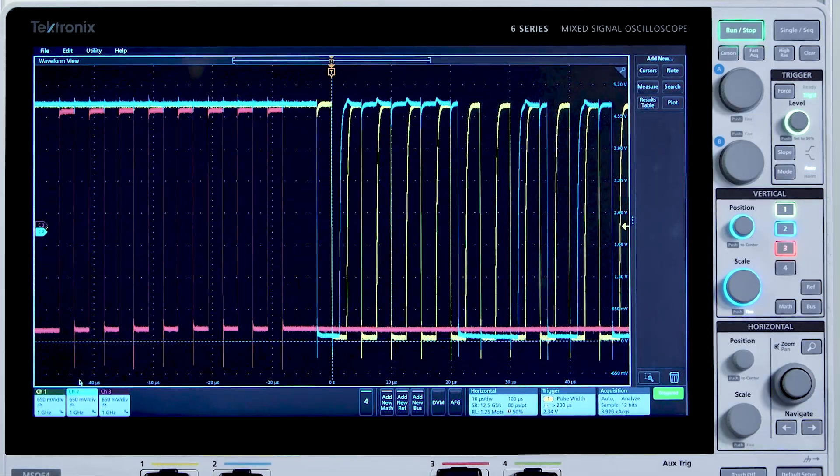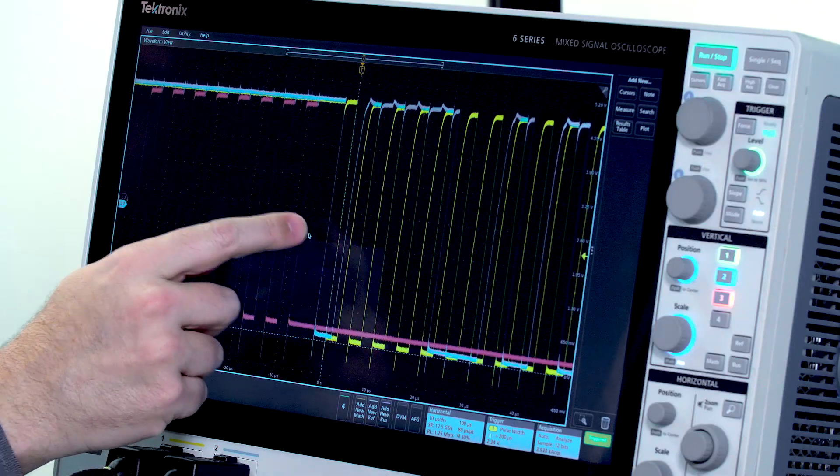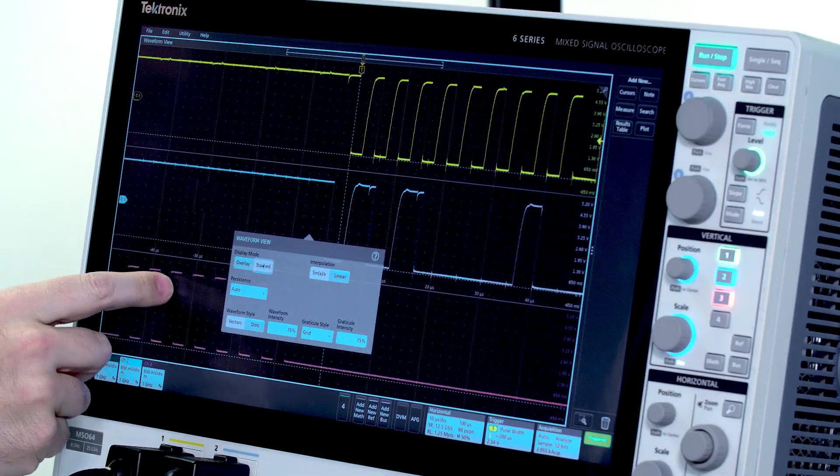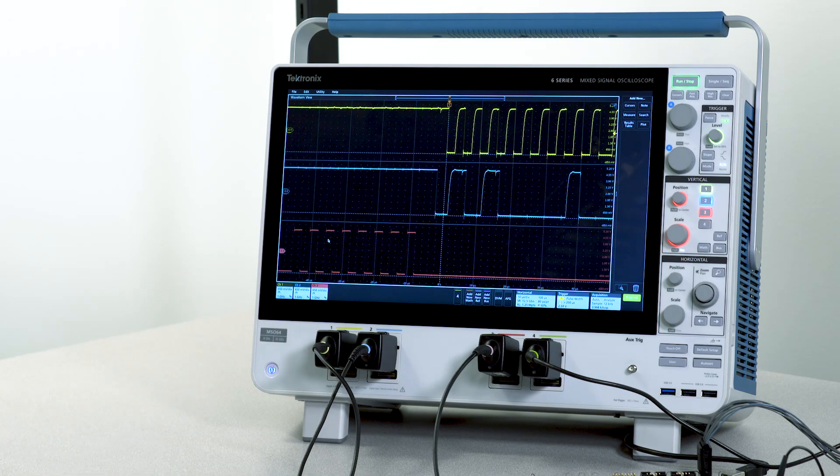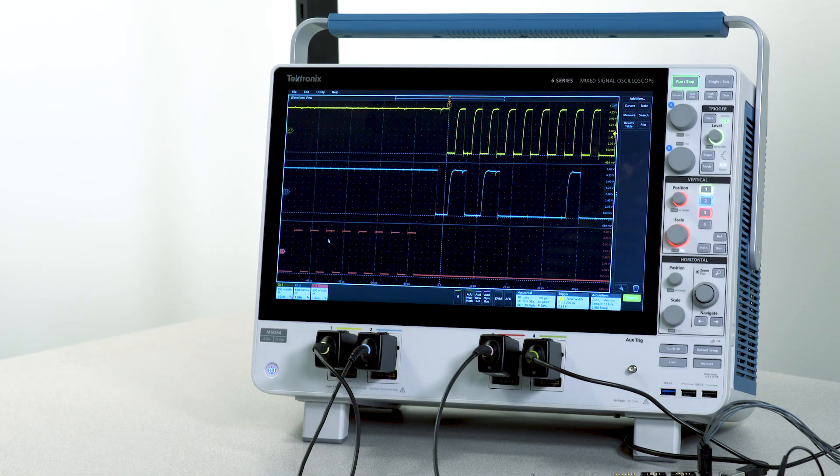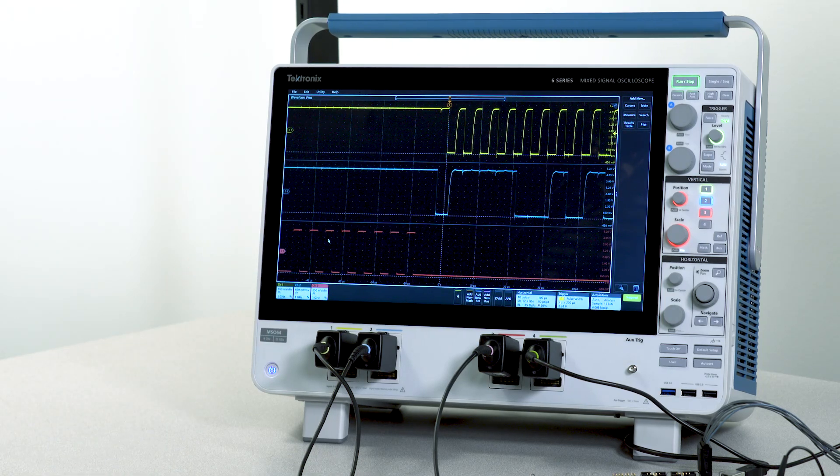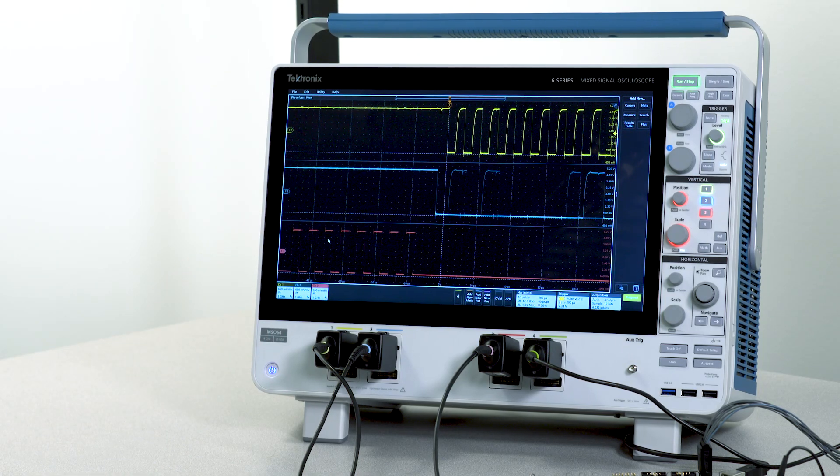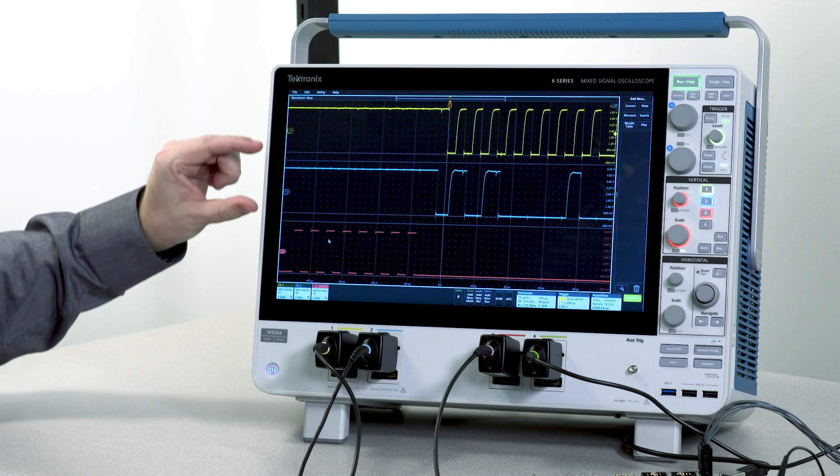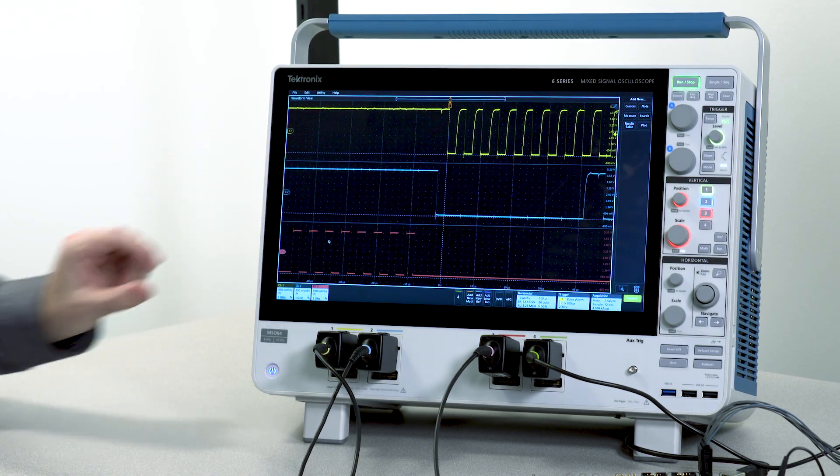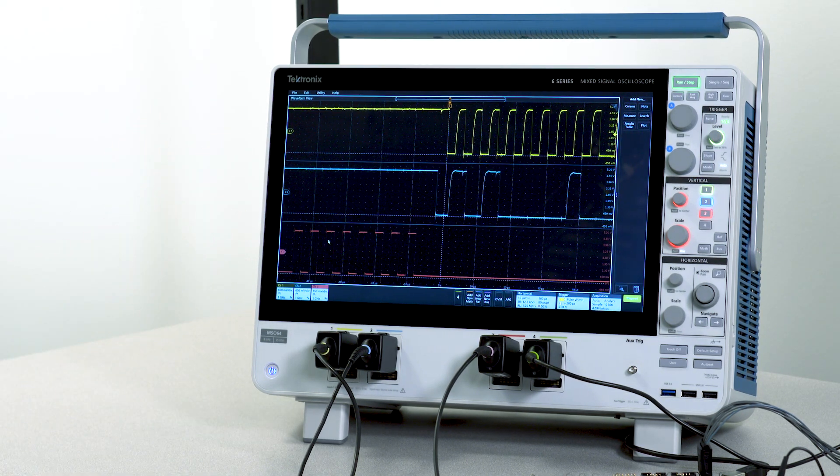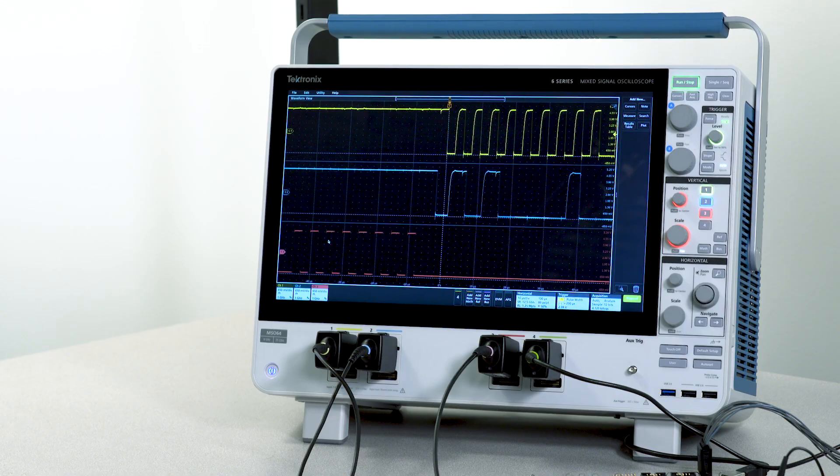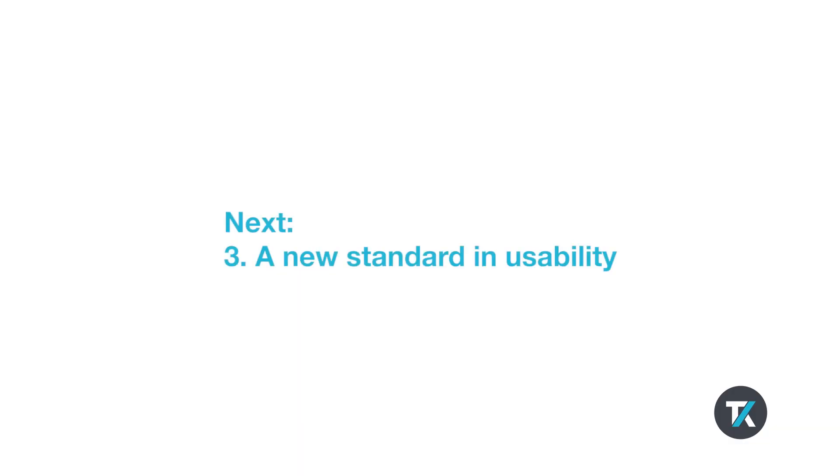I can switch to a stack display mode. This helps you get the most out of those 12-bit A to Ds by allocating separate full resolution graticules for each waveform. Each graticule represents the full dynamic range of the ADC.